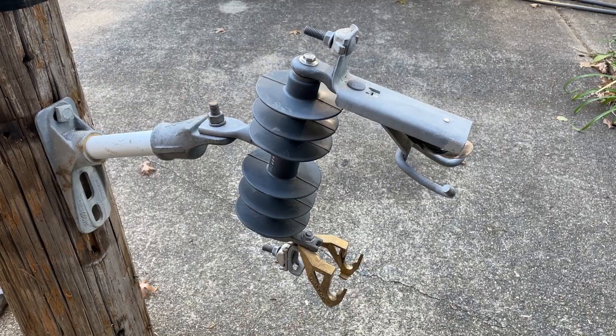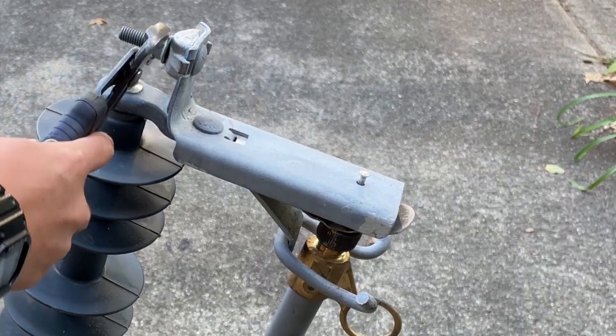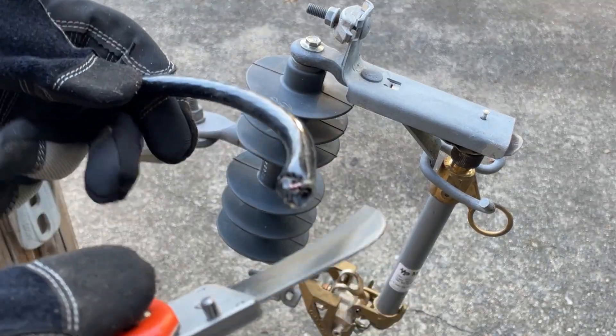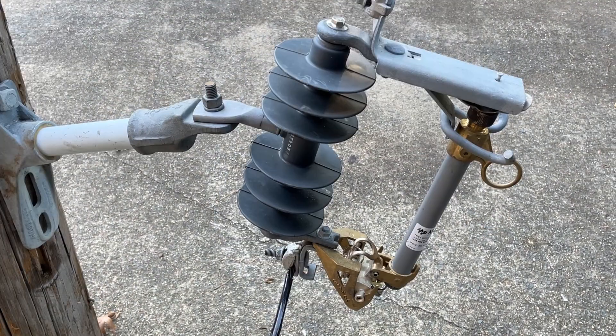Now that that's complete, I can put this in the cutout and then I can put my leads on here. I have this door closed and the leads hooked up. Now we are going to blow the cutout using the welder.